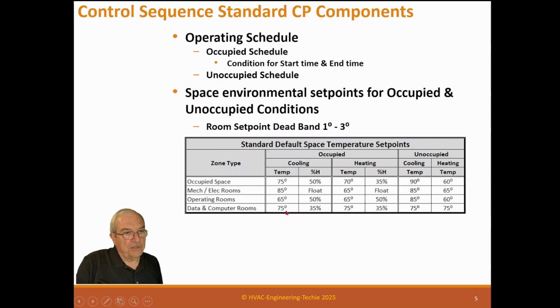Now, there are some changes out there. This used to be 72 degrees, but they've learned that they don't need that cold a temperature at the servers. They can have up to 90, 95 degrees. So this could maybe even go to 80 degrees, but 75 is good, even 78. But the standard right now is 75 degrees. Unoccupied for cooling is 90. Heating is 60. 90 to me is a little high for a setback temperature. I like 85 better, but these are all settable by the operator.